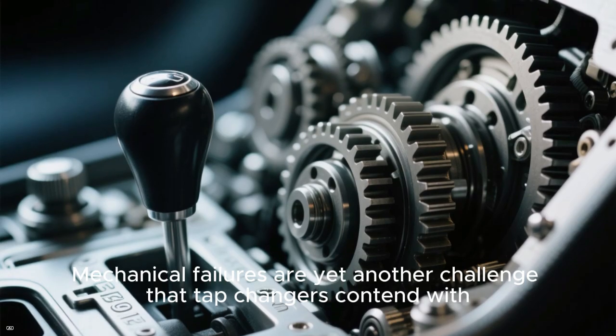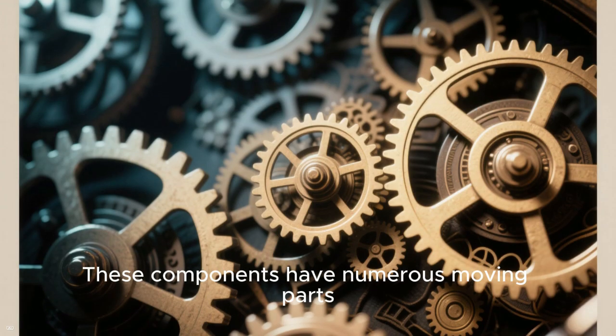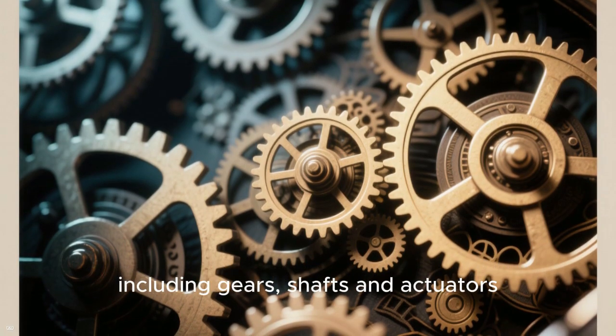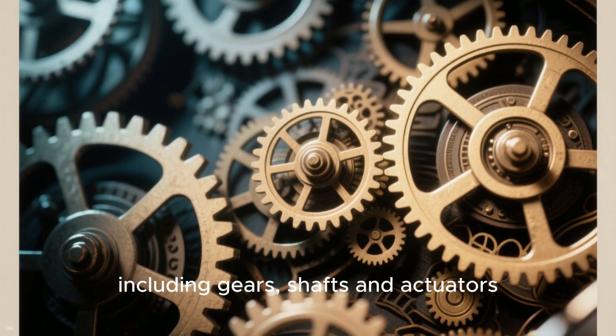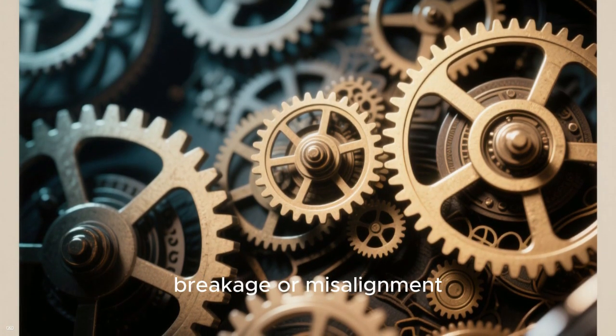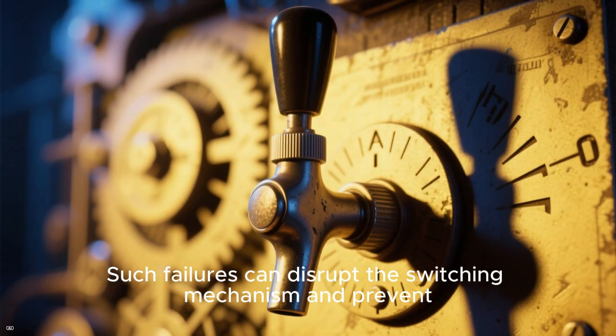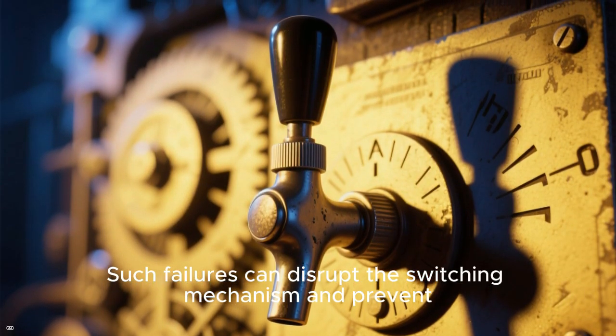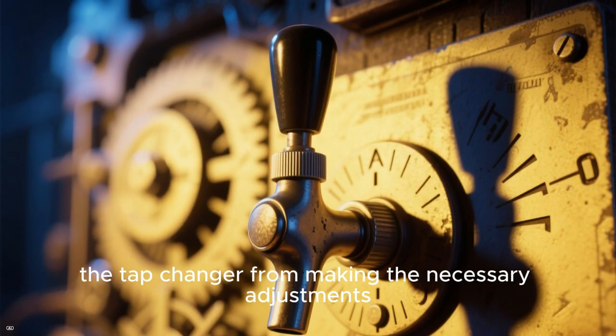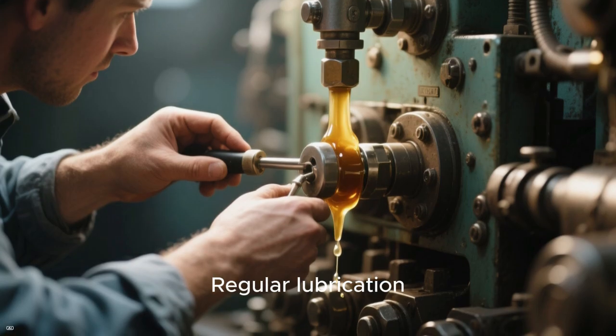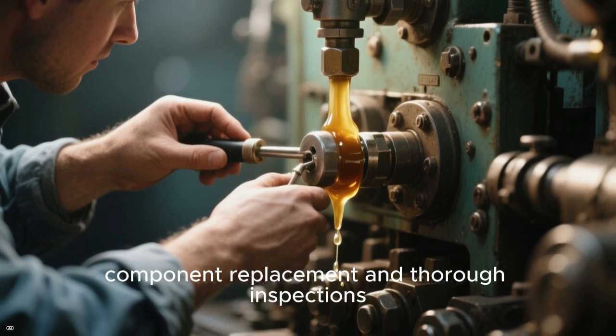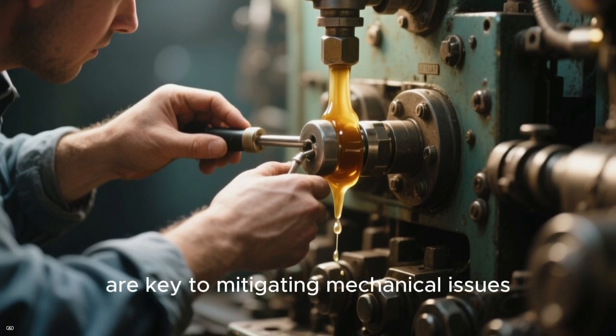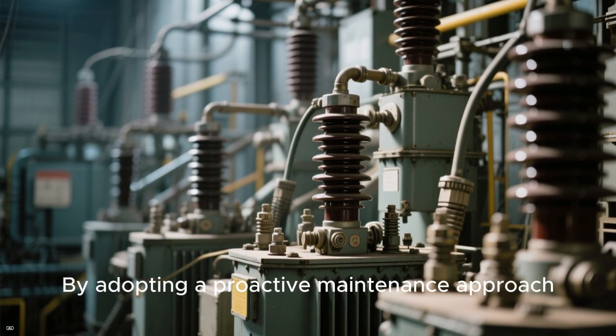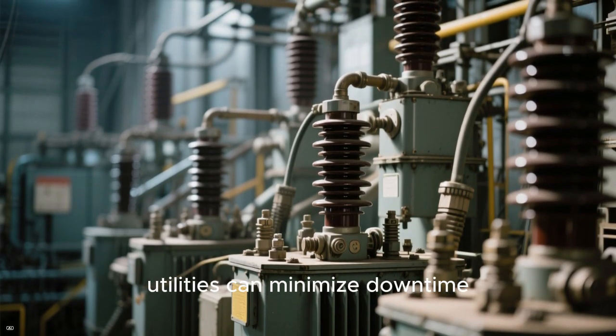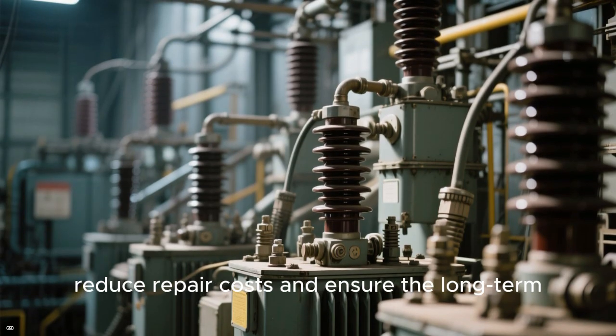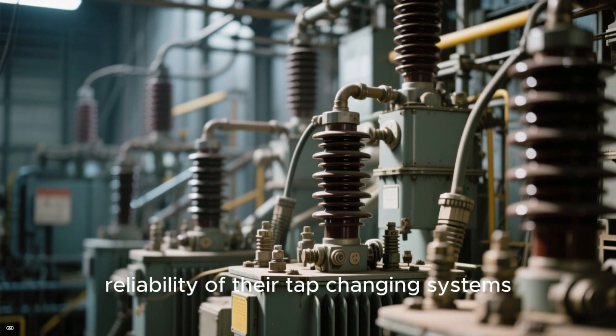Mechanical failures are yet another challenge that tap changers contend with. These components have numerous moving parts, including gears, shafts, and actuators, which are susceptible to wear, breakage, or misalignment. Such failures can disrupt the switching mechanism and prevent the tap changer from making the necessary adjustments. Regular lubrication, component replacement, and thorough inspections are key to mitigating mechanical issues. By adopting a proactive maintenance approach, utilities can minimize downtime, reduce repair costs, and ensure the long-term reliability of their tap-changing systems.